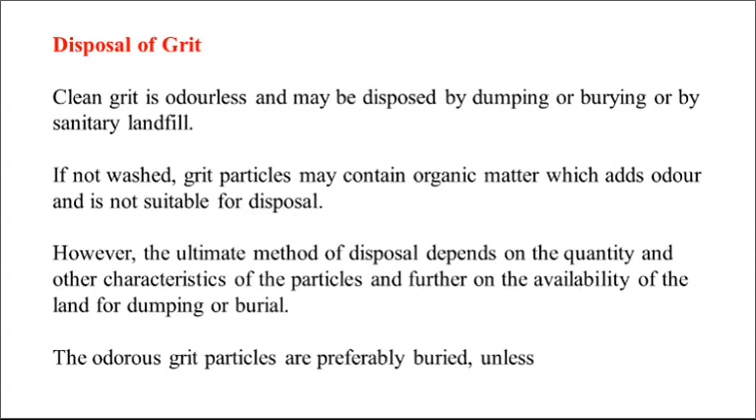Next one, disposal of grit. Clean grit is odorless and may be disposed of by dumping or burying or by sanitary landfills. If not washed, grit particles may contain organic materials which add odor and are not suitable for disposal on open lands.